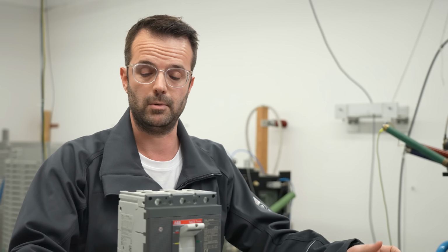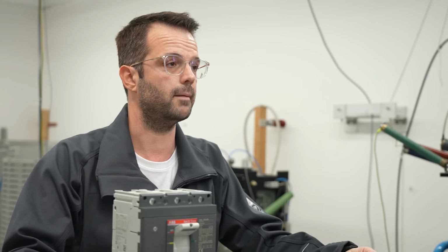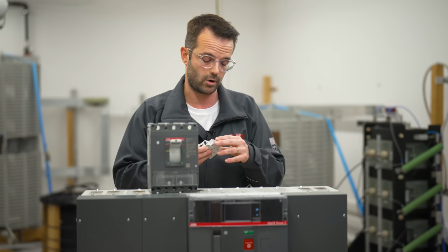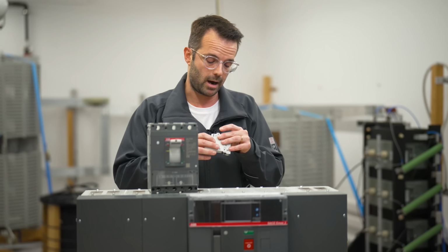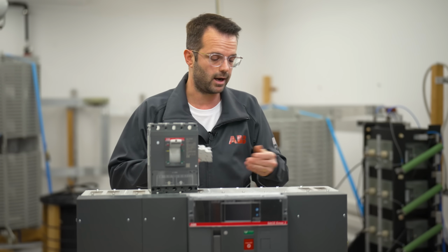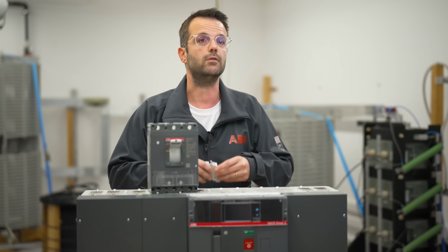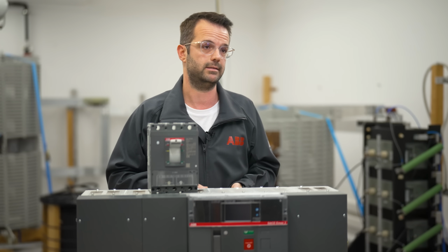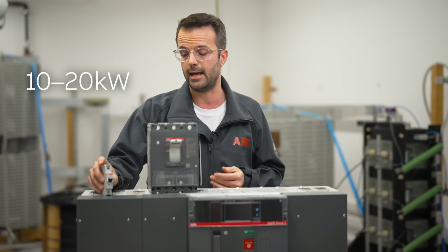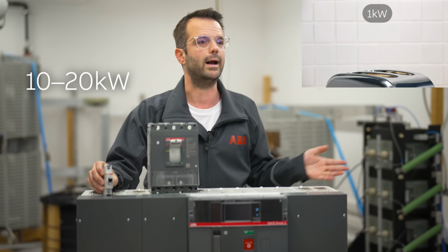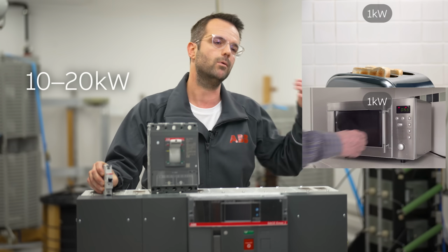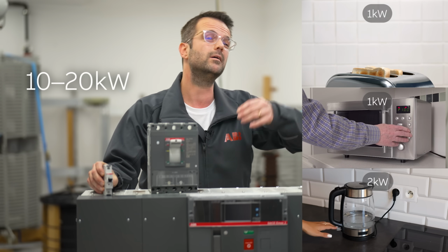The power we are talking about here is pretty big. During a short circuit interruption, due to the electric arc I mentioned before, it can develop power in the range of 10 to 20 kilowatts. Just to give you an idea, your toaster is 1 kilowatt, the microwave 1 kilowatt, the electrical kettle 2 kilowatts.